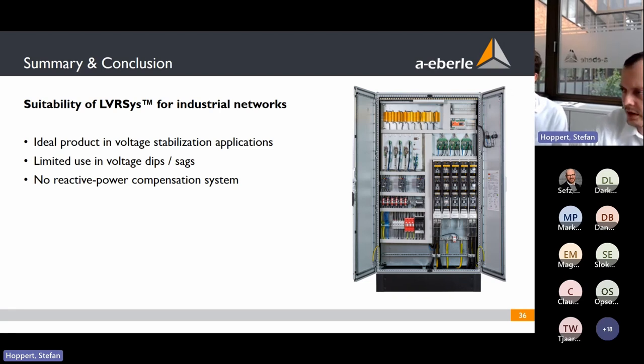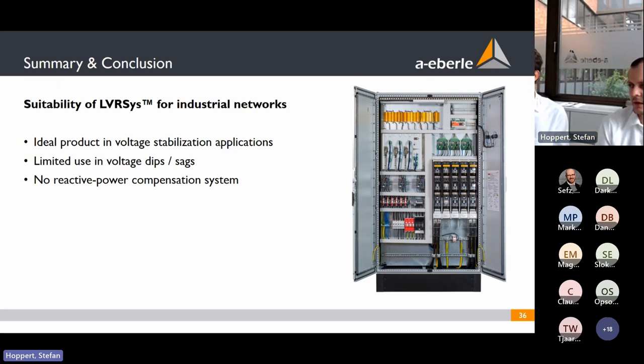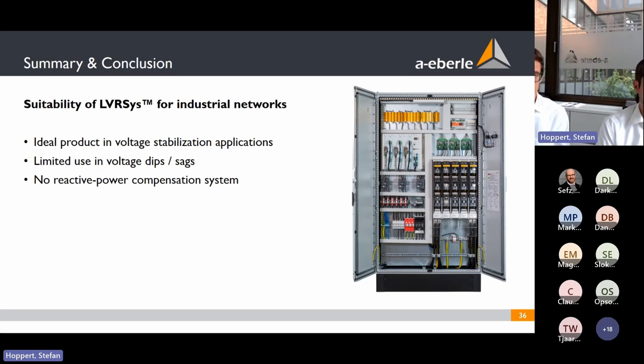Q&A: How long does it take to normalize voltage if the voltage dip is 40 percent? With a 20 percent boost system: if the dip is 40 percent, the remaining voltage is 60 percent. Boosting 60 percent by 20 percent gives 72 percent — we cannot restore it to nominal. The voltage remains at 72 percent until the dip naturally ends, as we have no energy buffer to compensate such deep dips.